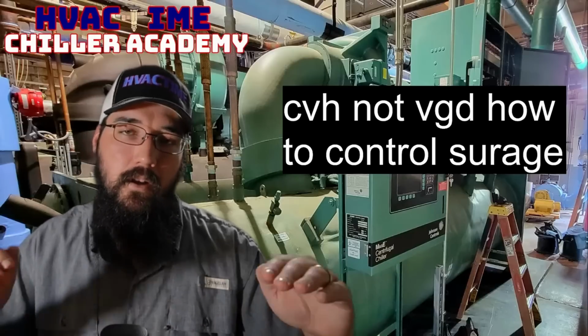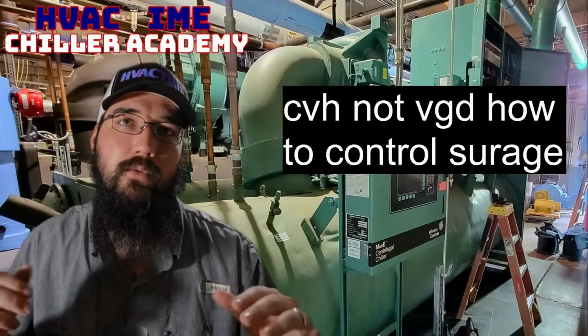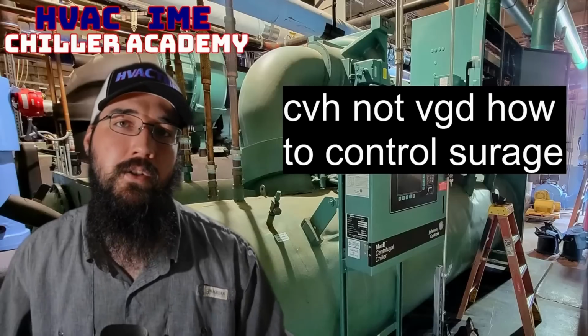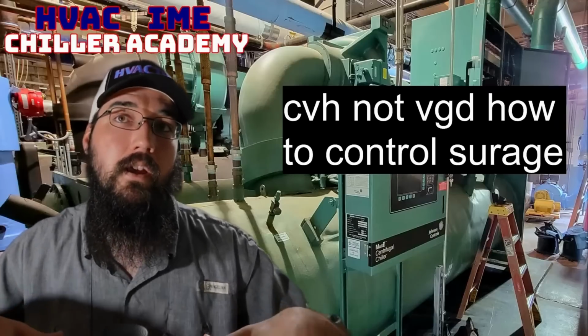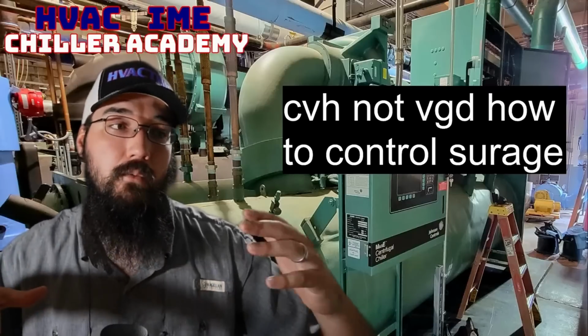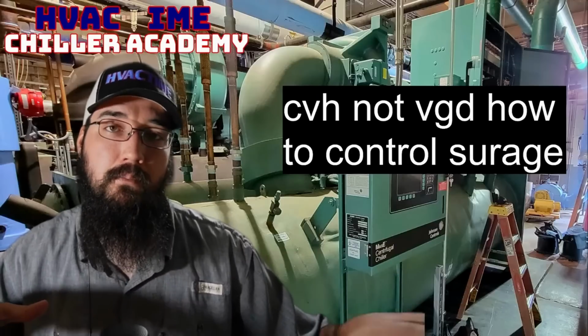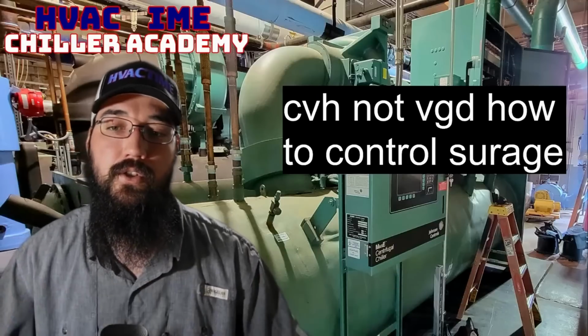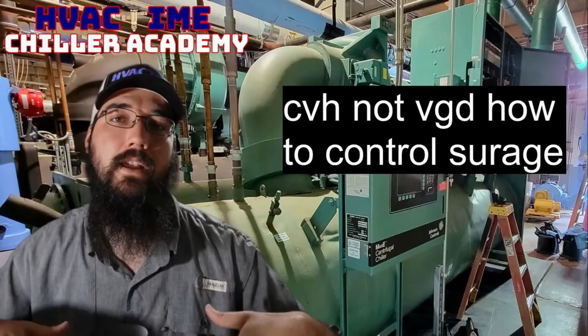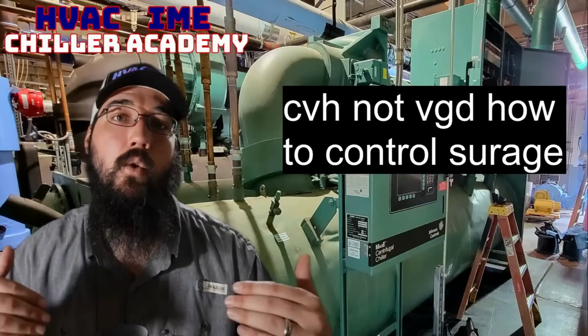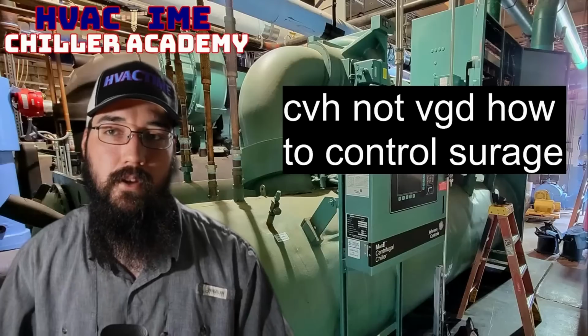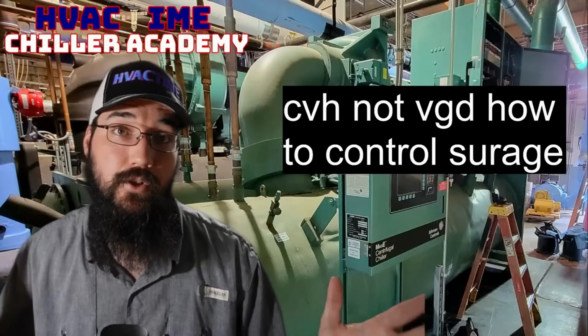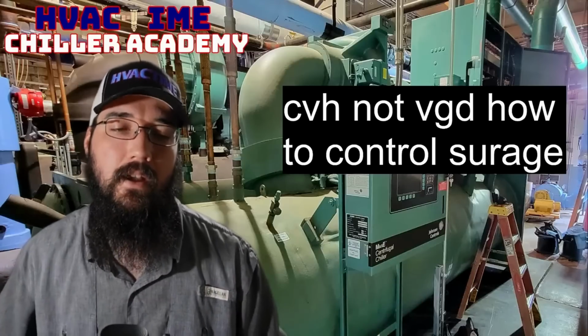So by lowering a current limit, we can artificially limit how much the compressor is allowed to ramp. We're not going to make leaving water set point, but we don't need to at this point. We're in a surge state. We need to know how we can troubleshoot this machine to figure out why it is surging. We've determined that a surge is happening. Now, why is it happening?